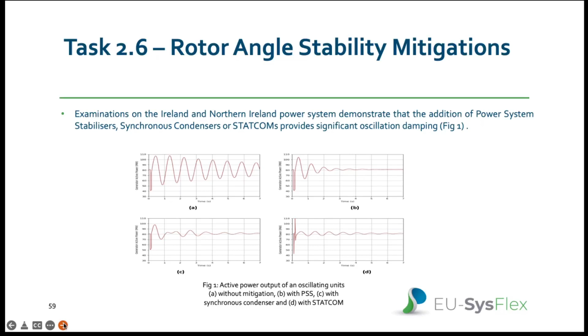Analysis in this task showed that large quantities of these technologies will be required for this localized issue. We conducted further studies showing that the most appropriate option would be consideration of an operation policy, whereby under specific circumstances and system conditions, the unit commitment itself would be modified, dispatching down the unit that loses synchronism while increasing the output of another generator to accommodate the shortfall.